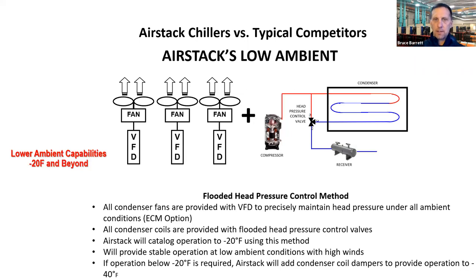What a modular chiller does, we have individual modules that could either have both fans controlled with a VFD or be ECM fans. We have a loop system with a valve control. We call that flooded head pressure control. So we're gonna drive refrigerant around, push, push, push with our compressors. We're gonna store it in a very oversized receiver so that when that compressor is ready to start, we've moved that refrigerant to where it should be.